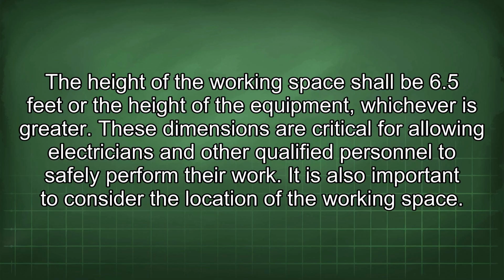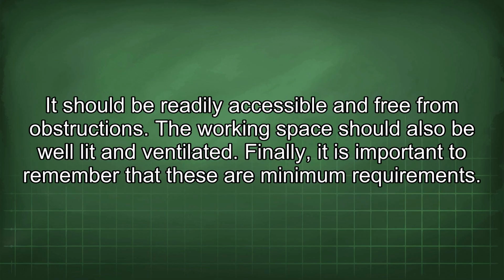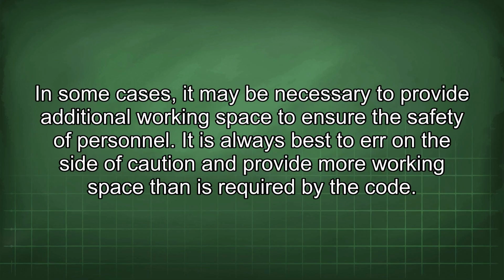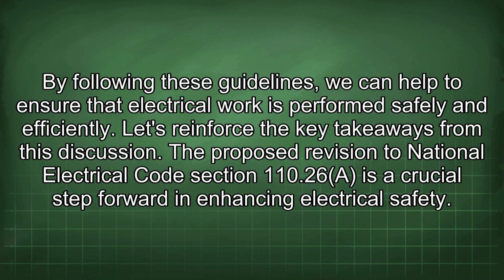It is also important to consider the location of the working space. It should be readily accessible and free from obstructions. The working space should also be well lit and ventilated. Finally, it is important to remember that these are minimum requirements. In some cases, it may be necessary to provide additional working space to ensure the safety of personnel. It is always best to err on the side of caution and provide more working space than is required by the code. By following these guidelines, we can help to ensure that electrical work is performed safely and efficiently.